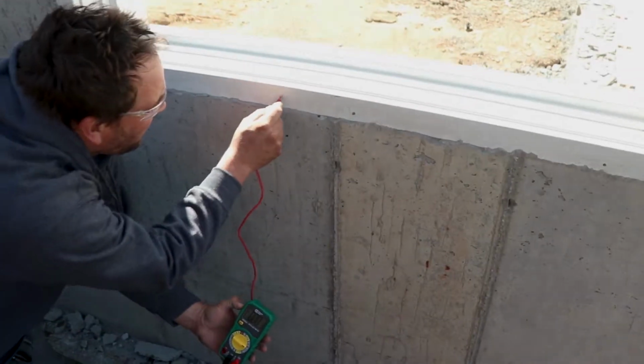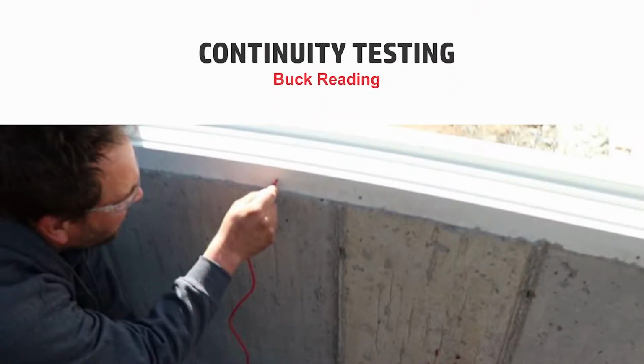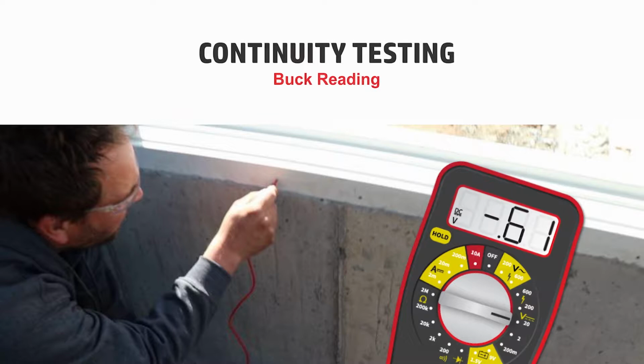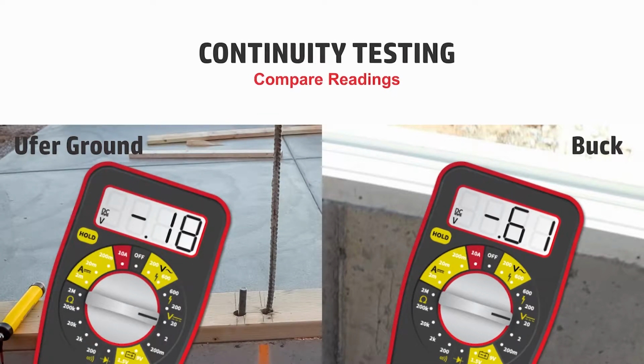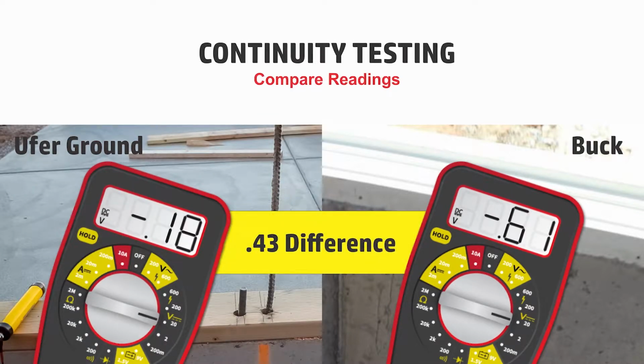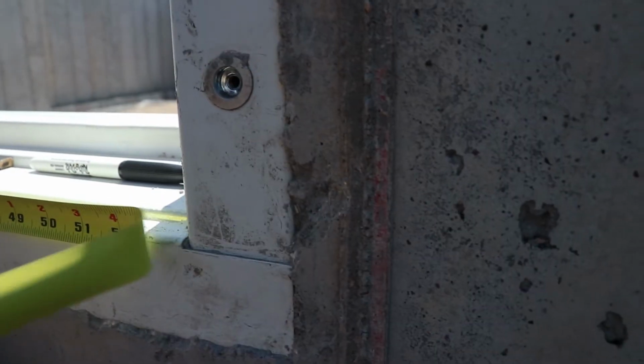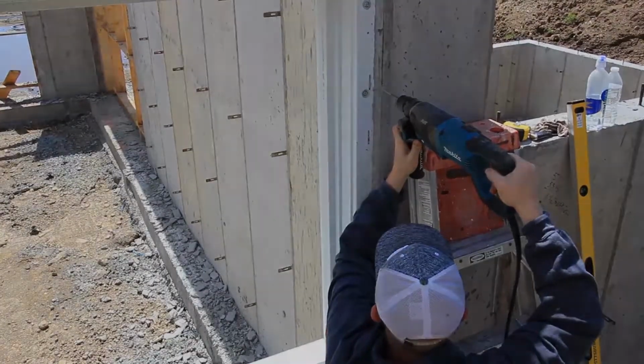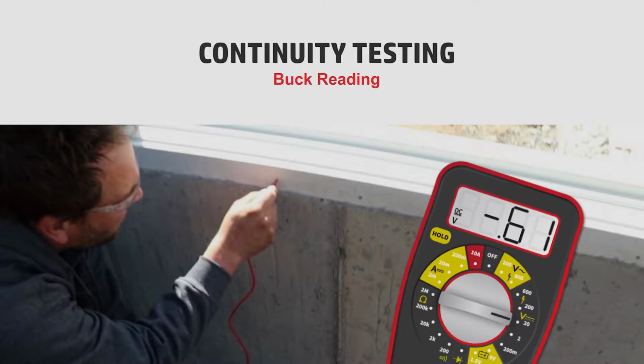Test the window buck. Scratch through the finish with the red lead and take a reading of the buck. On this home, the continuity test on the buck read -0.61, a 0.43 volt spread. If you do not achieve a 0.20 or greater spread, it is an indication that a metallic bond was created and the buck is hot. Corrective measures would need to be taken, but since the buck read -0.61 and is not hot, buck mount installation can proceed.